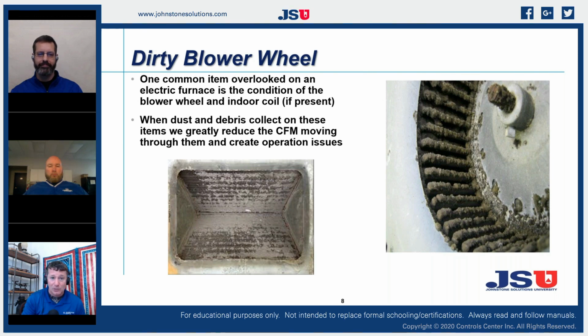If it's a constant torque, it's trying to maintain a certain torque, a certain load on that motor, and it's going to draw more amps trying to do that. So if I measure the amps on my motor and I go, man, my motor is working really hard to try to move this 1200 CFM, and I just took a temperature rise and it's saying that I'm actually probably only moving 1000 CFM, I need to go figure out why my air is not moving, right? That's when I can get into looking at my coil and looking at my blower wheel to see what type of airflow I have in my system.